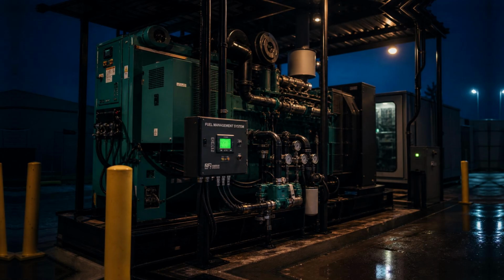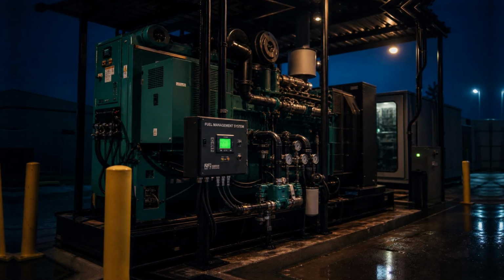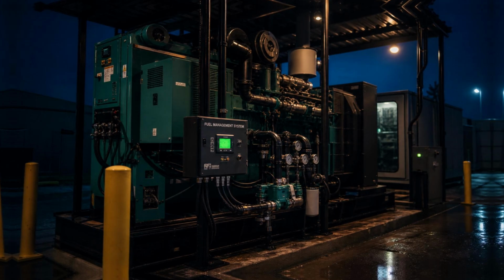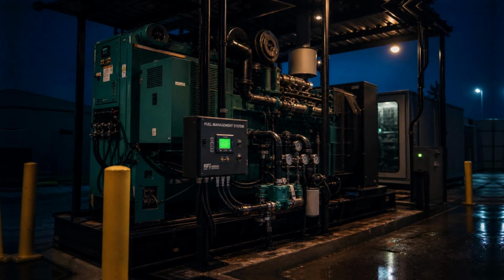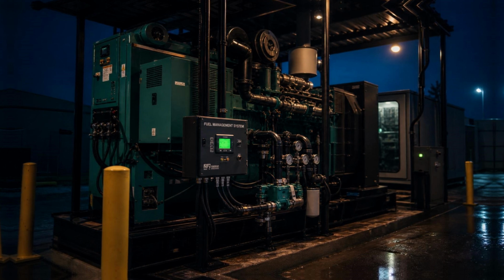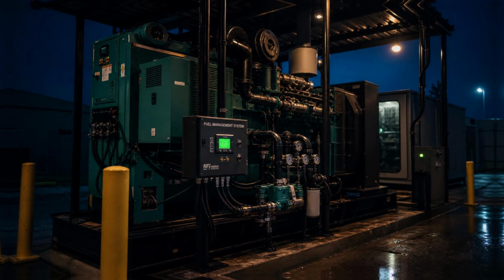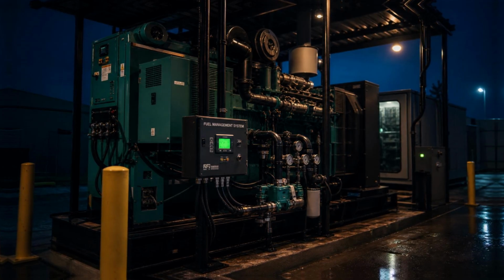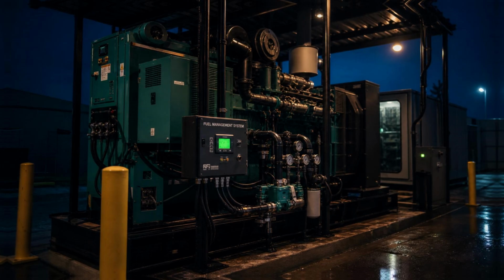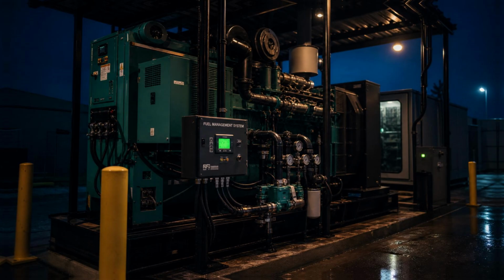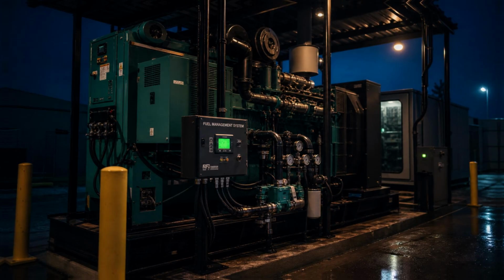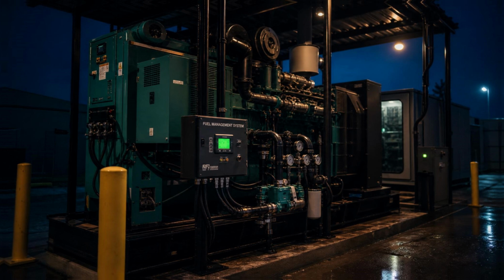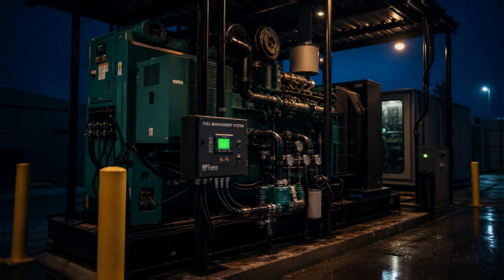They can cause anxiety. They can disrupt rest that is already fragile. They can produce questions and concerns that compound the stress of being in a hospital at all. The emergency power system of a well-designed hospital takes this into account. The goal is not merely that critical equipment keep running, though that is the essential goal, but that the transition from utility to emergency power be, from the patient's perspective, as imperceptible as possible, that the monitoring equipment does not alarm unnecessarily, that the corridor outside the room does not go dark before the backup lighting activates, that the sounds and lights of the clinical environment remain as steady and as reassuring as they are expected to be.